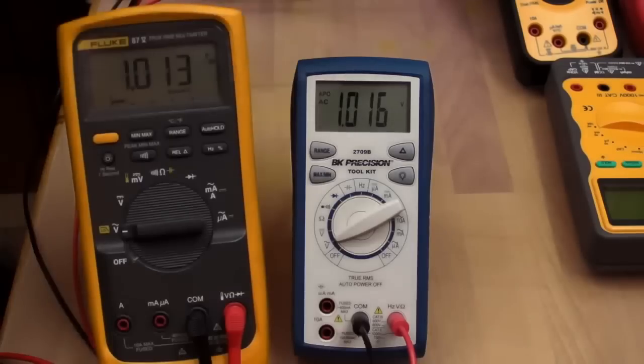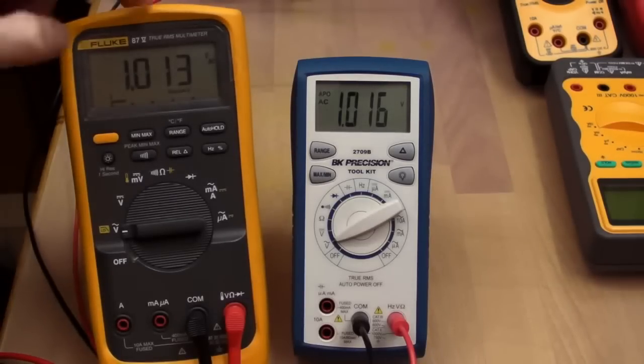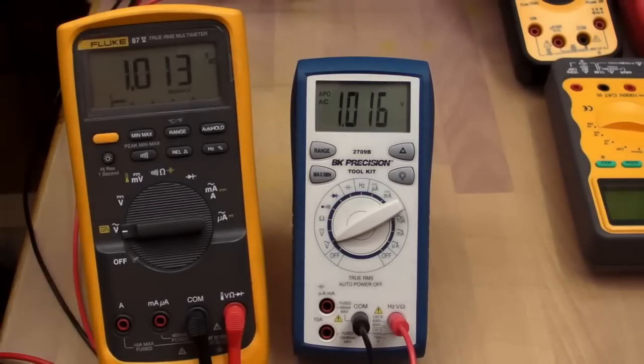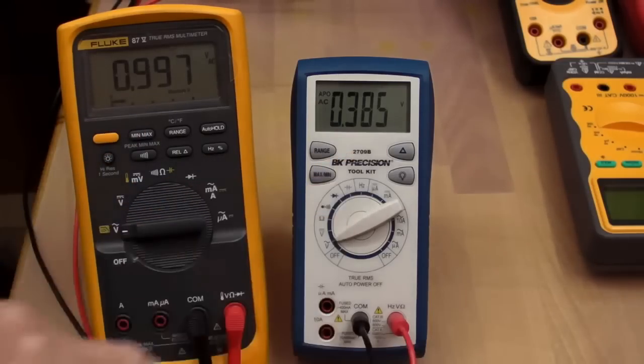We've got the BK Precision here, and as you can see, it's a 1 volt RMS amplitude, pretty close to spot on at 300 hertz. Now let's increase that to 3 kilohertz, and as you can see, the BK Precision starts to drop a little bit. But the Fluke doesn't, and now we're up to 30 kilohertz, and as you can see, the Fluke's still reading, but the BK Precision has dropped right down.